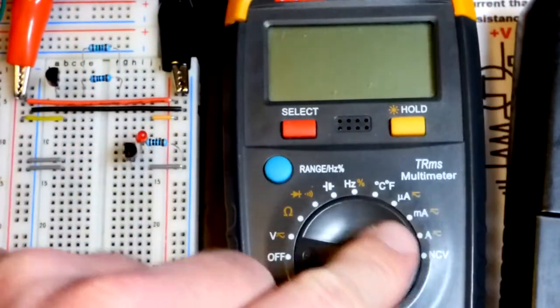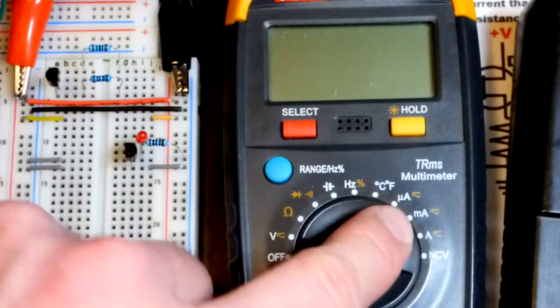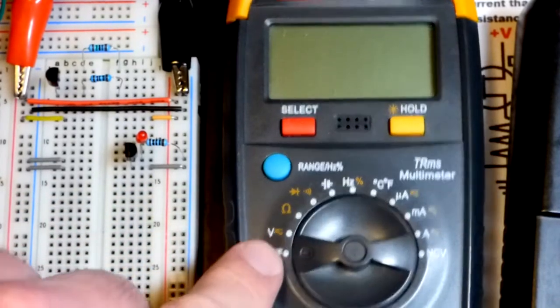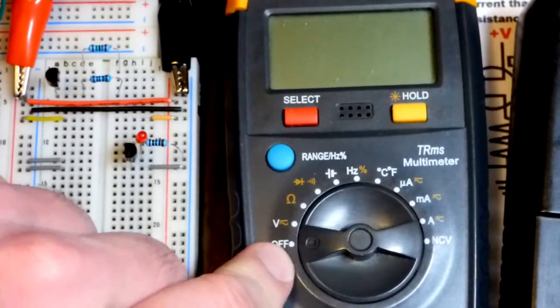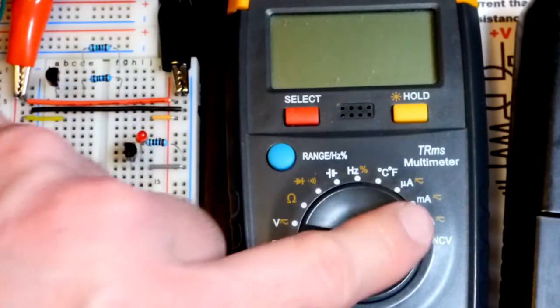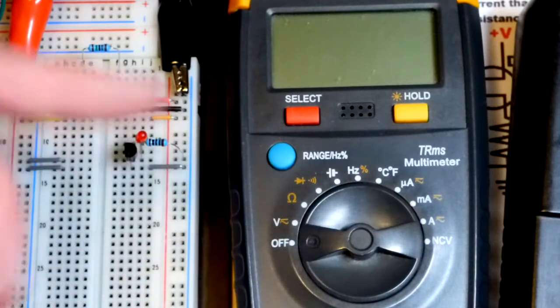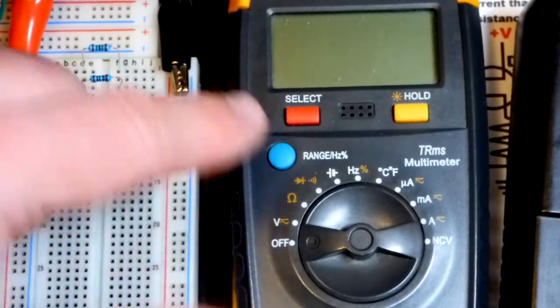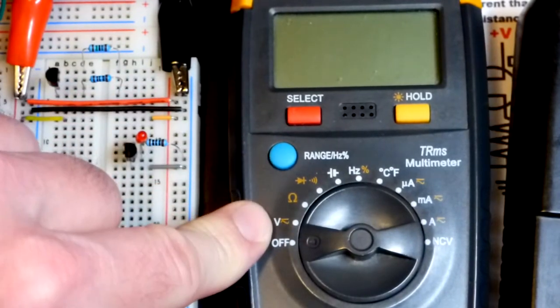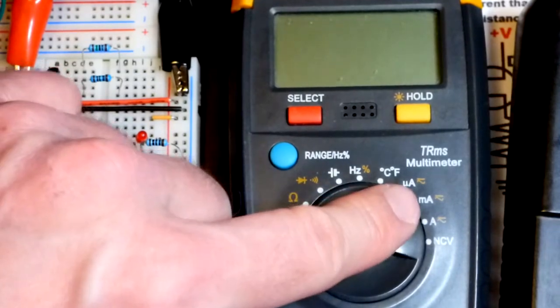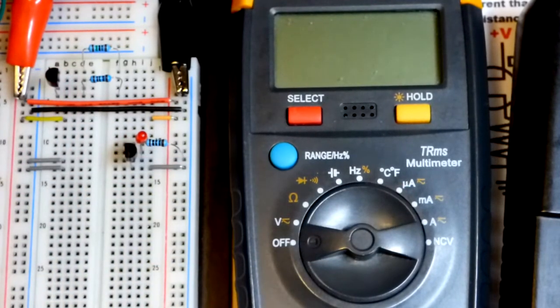So I'm going to turn the meter off to make sure it's off. Especially when you measure current, you want to get it off of measuring current. Off is preferred if your meter has an off dial. Well, if it just has a power button it's good to set the meter to voltage. So that when you go to measure something you have less chance, almost no chance of damaging it if it's set to voltage. Whereas you have a good chance of blowing a fuse or something if it's on milliamp. So I try to mention that in almost every multimeter video that I do. It's a good thing to remember.